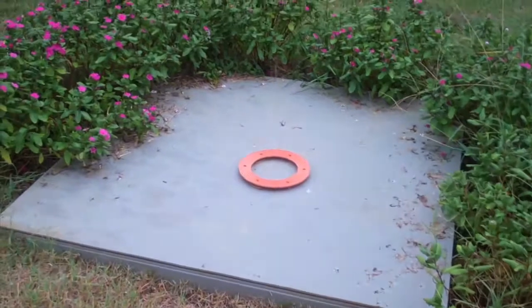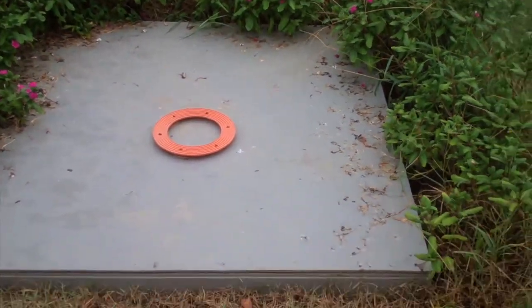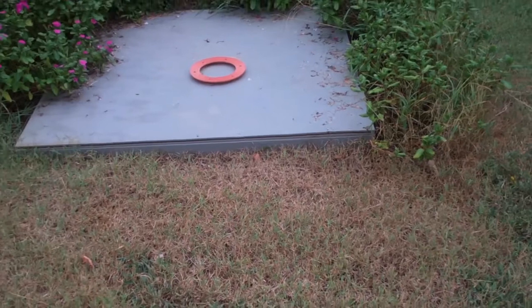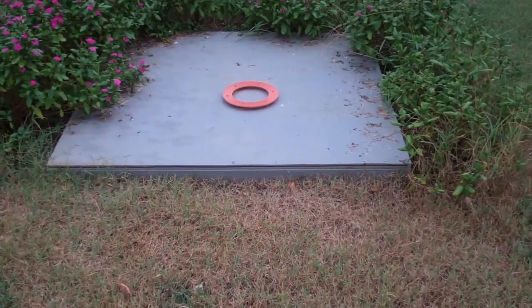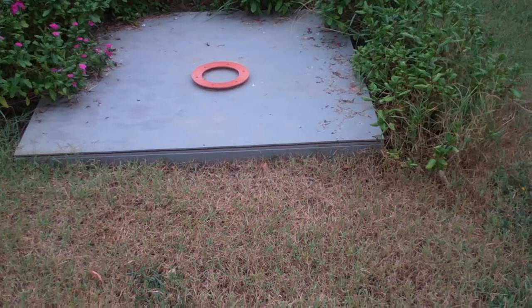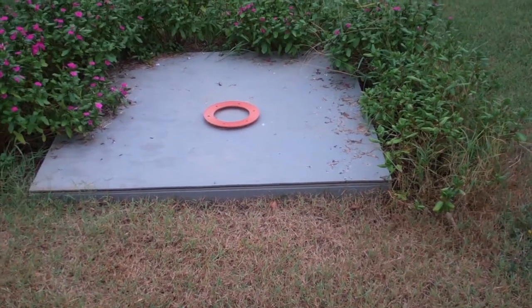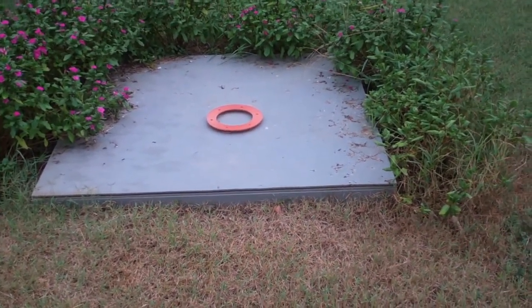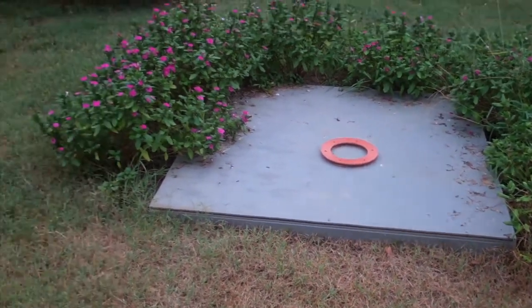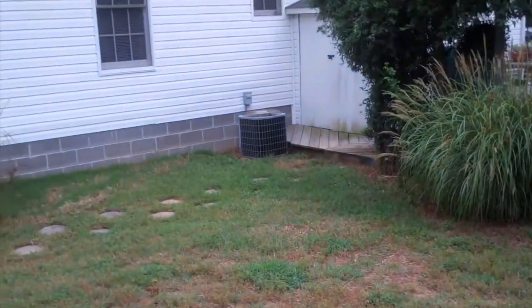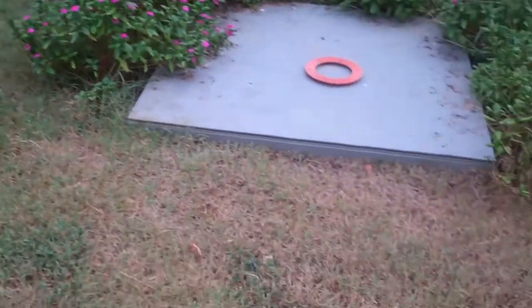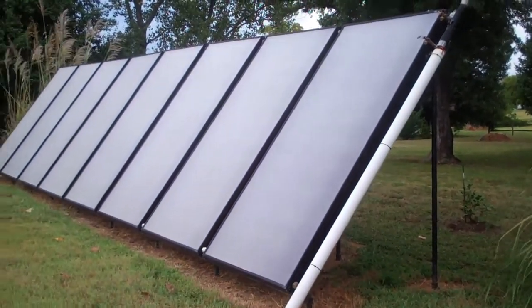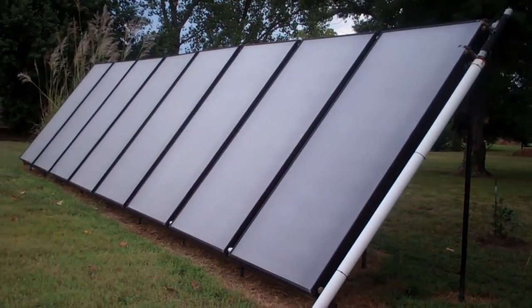And this is part of the Virginia Heat Store project, which instead of using hot water storage in a tank, we're storing it in a solid medium, sand. So the closed loop goes into the sand. The heat store is 8 foot by 8 foot by 8 foot, so it's 15 cubic meters. And then there's a separate loop that takes the heat out of the heat store and transfers it into the house for space heating. So that's the Virginia Heat Store. First one in the United States, developed along with VCU. We're hoping to use it for affordable housing projects in Virginia.